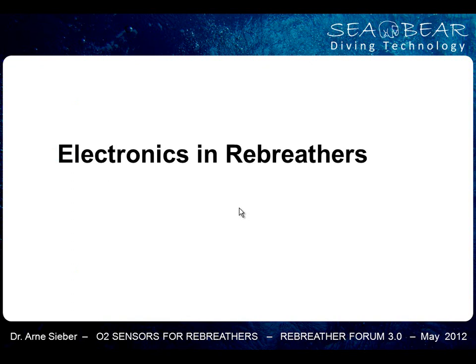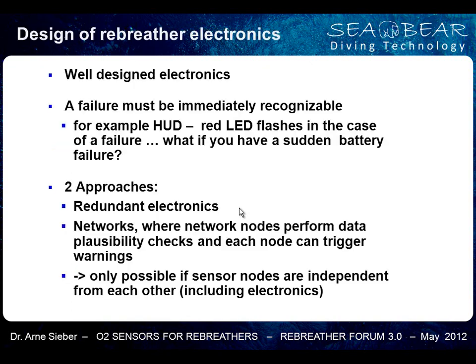Electronics in rebreathers. This is my next point. Design of electronics in rebreathers. A very important thing is that the electronics is well designed. Important is that a failure is immediately recognizable. As an example, if you have a head-up display with a red light, as a very simple example, and you have learned that the red light flashes if there is something wrong with the rebreather.